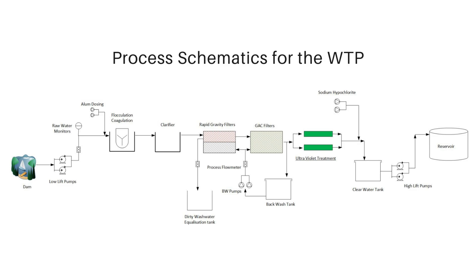From the dam we need low lift pumps, or raw water pumps, that will pump the water from the dam to the first process unit. As we will see when we look at the hydraulic profile, all these units should be arranged so that we pump water from the source to the first stage, then from the second stage onwards the water flows by gravity. The water is pumped from the low lift pumps to the flocculation tanks.